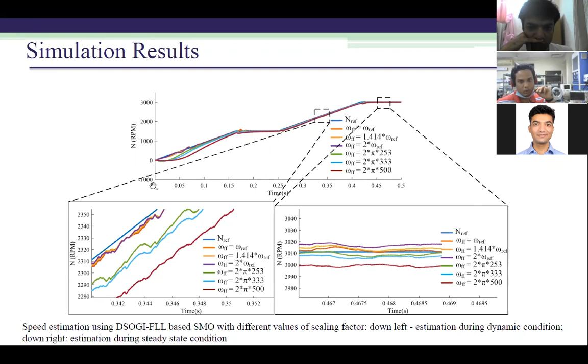during the dynamic condition, the higher value of feed forward gain is almost nearer to the reference speed, whereas during the steady state condition, the lower value of feed forward gain is giving better performance, almost nearer to the reference speed. So in order to optimally choose one, we have chosen the middle value, which is root 2 times omega ref. That's how we have chosen the scaling factor for the FLL feed forward gain.